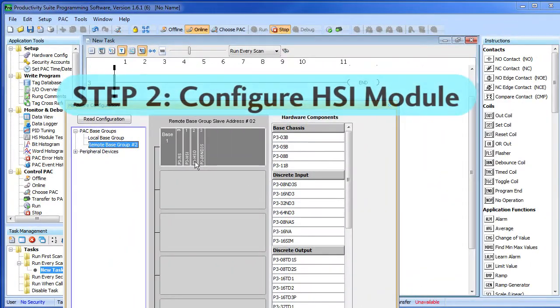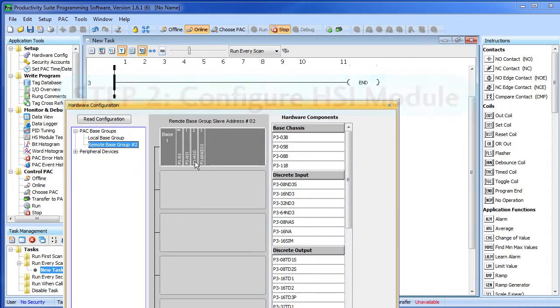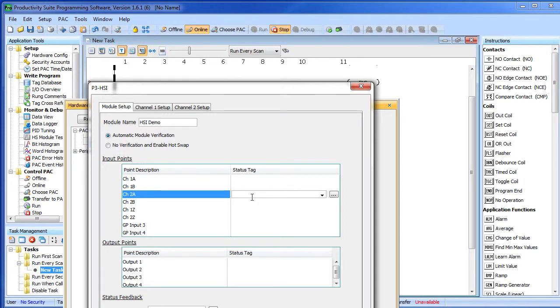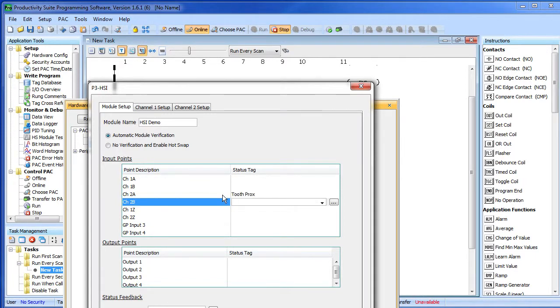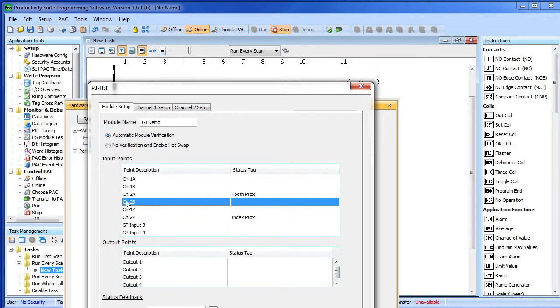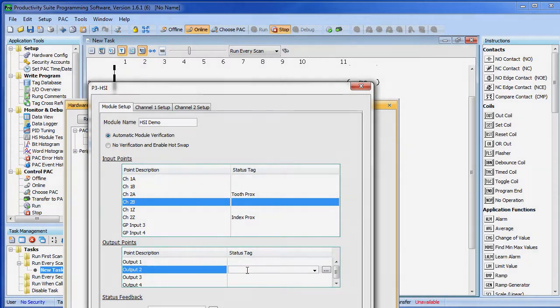Step 2 – Configure the HSI module. Double click on the HSI module and give it a name – how about HSI demo? We have our tooth counting prox sensor connected to channel 2A, and our index proximity sensor is connected to 2Z. Note that you can't use 2B for counting pulses – it's strictly used for direction, like when we use encoders. We're also going to use output 2 to drive our strobe light – let's call that prox strobe.